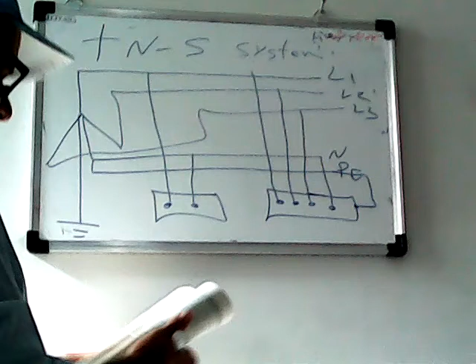Here with protective earth, you can use multiple earth such as pipe, pile, iron construction, body of your equipment. You can use other things to add to your protective earth. For that reason, we have much less resistance of RB to act on protective devices such as fuses, as talked about before. Okay, that's the advantage of TNS.